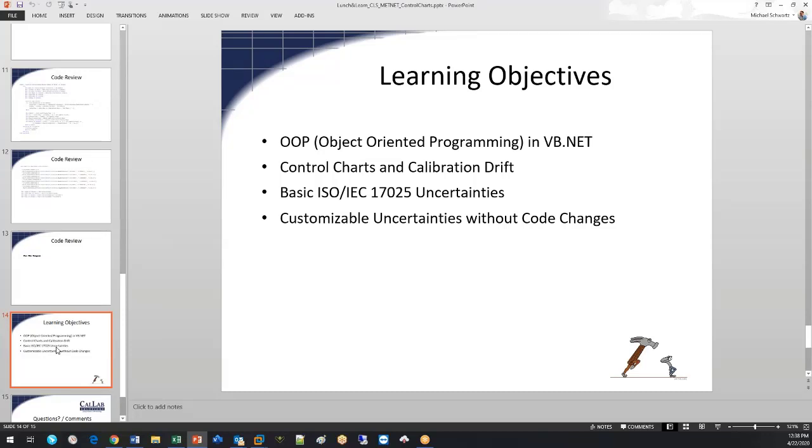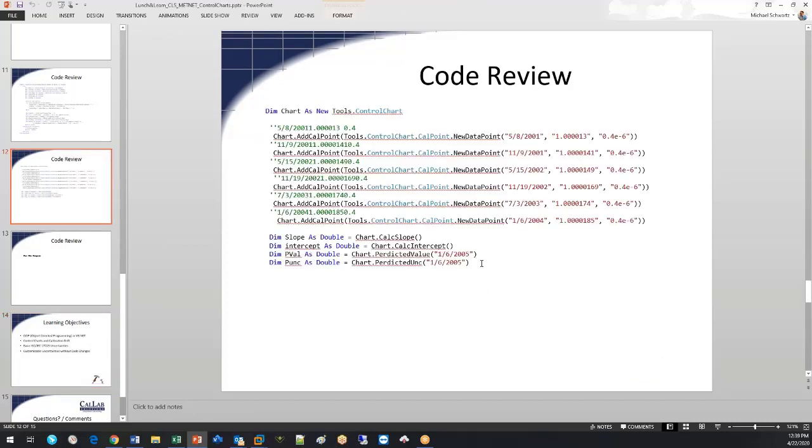The ISO 17025 uncertainties, there's going to be more that you have to include in this, but you can see how the data files that you're using in code can be passed off to the auditors, and you've got that separation between the code that you're running and your data files and how you can report something out. So now inside of your code, when you want to get the uncertainty for a value and a calculated value, you can reach into this line of code and you can grab for whatever date you're running the calibration.